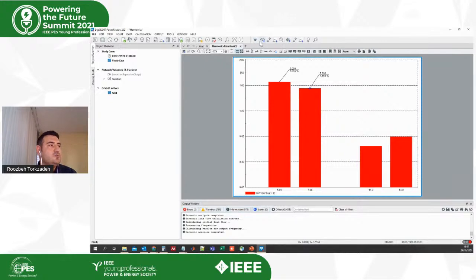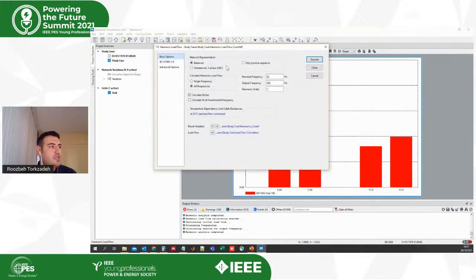Also, we can do one thing more with this harmonic load flow. Basically, this load flow is a regular load flow, but for a different range of frequencies. So when we have the result for a different range of frequencies, with a Fourier transform we can convert those frequency values into a time domain signal. And the thing that I want to mention is that with PowerFactory, we can create some waveform signal.